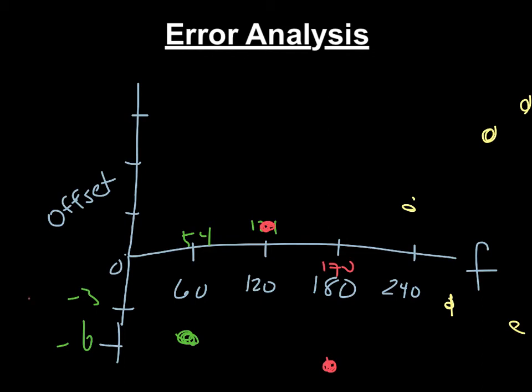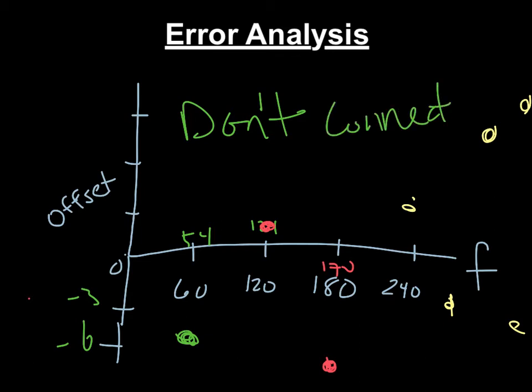Don't connect dots. Because what happens at 60 hertz doesn't affect what happens at 120. You're just saying that at these values, at 60, 120, 180, and 240, I am off by this much. You do not connect your dots. Now, the lab says to go to 420. I have seen students get in the low thousands. It's not a bad way to spend a day. It's pretty fun.